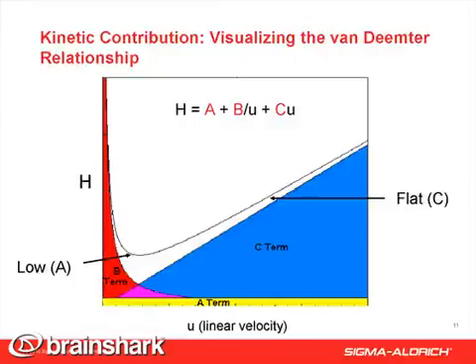So what can column manufacturers do to minimize the A term and C terms? One, use small particles. Two, minimize the space between particles. That is, making sure that the bed is packed very well and uniformly. And three, reduce the mass transfer into the stationary phase and particles.